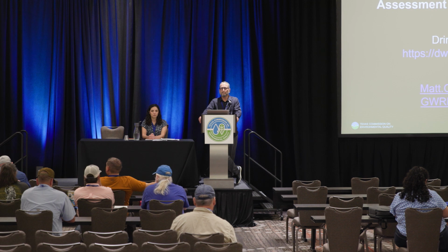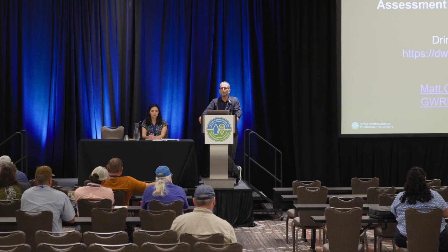Okay, thank you. Five wells feeding into one line that goes to a ground storage tank, and you get a positive in the distribution system. Do you have to take five samples from all five wells? So yeah, if you have five wells and you don't have a triggered source monitoring plan, then yes, that would require all five wells if they were running. If any of the wells were not in use at that time, then they could document that on an inactive well form.